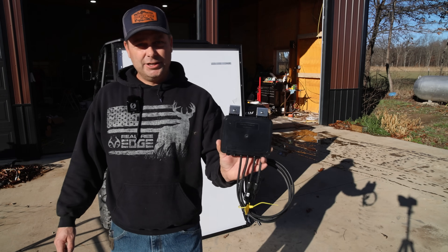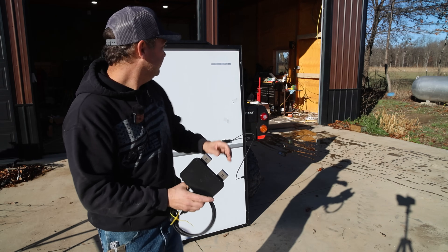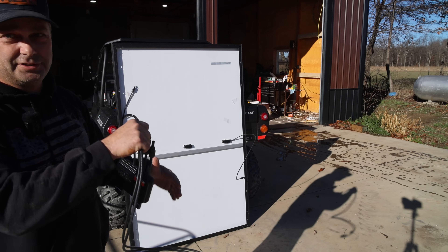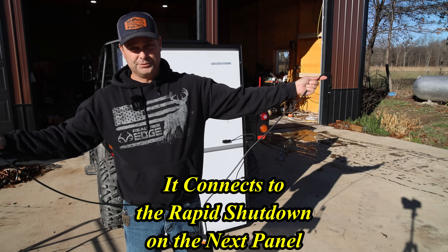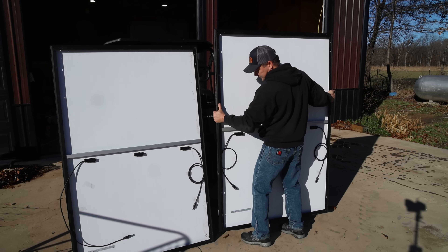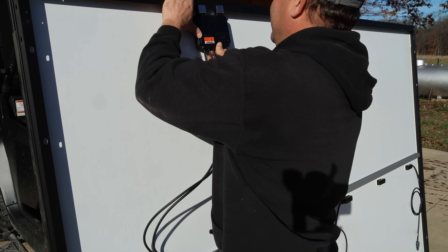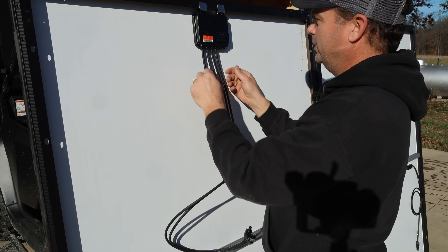This is the Tigo rapid shutdown module. It has little metal clips at the top made to slide and lock onto the metal frame of the solar panel. The module has two sets of wires: the short set attaches to the wires on the solar panel, and the long set is what you use to connect all the solar panels in series — connecting to the solar panels on each side. I'm going to put the shutdown module at the top of the panel in the middle. They push on hard so that they bite in and ground the module through the panel.